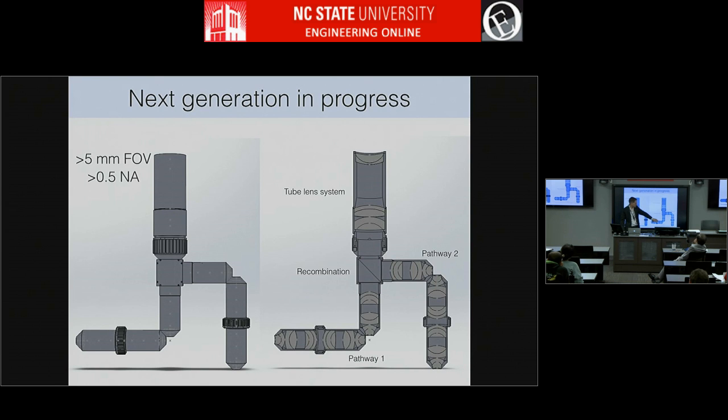And we've also decoupled the scanning. So we no longer simultaneously scan both beamlets at the same time. We can now independently scan them. One beam can scan a full field of view, and then the other one can scan one small postage stamp if you want. We've got 2 optical relays here: X mirror, Y mirror, scan lens. The beam recombination happens between the scan lenses and the tube lens, and it's based on polarization as well, so you can have the exact same wavelength of laser coming in both. And then this is a multi-lens tube lens system.